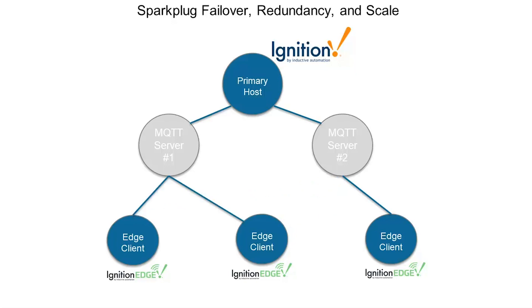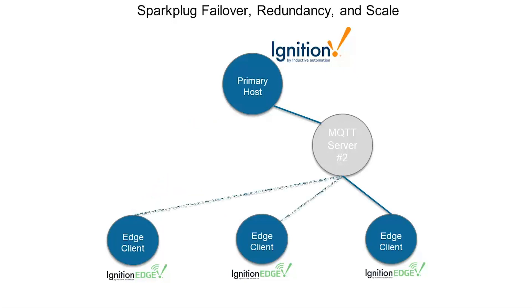Conversely, if that MQTT server went away, we would recognize that our MQTT session went away and walk over to other available MQTT servers. Using MQTT as our OT infrastructure, achieving high availability, redundancy, and scale is simply a matter of adding one or more MQTT brokers to your infrastructure.